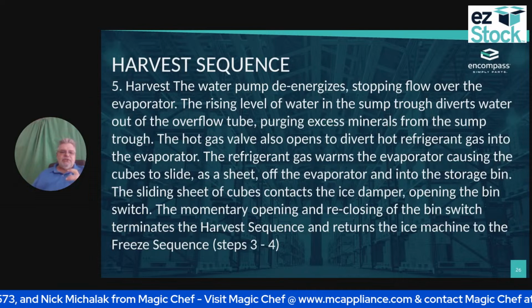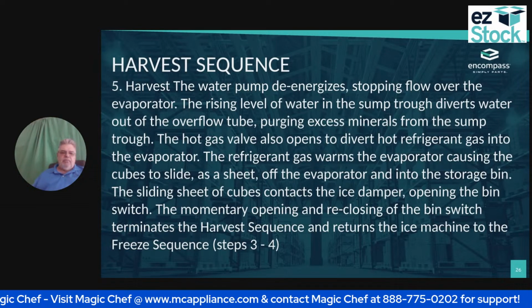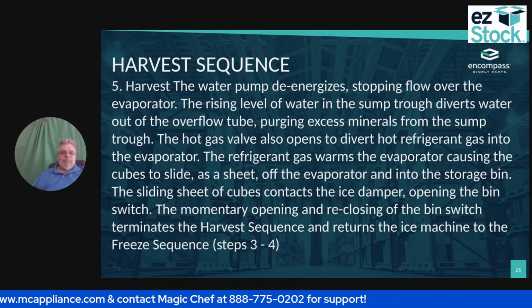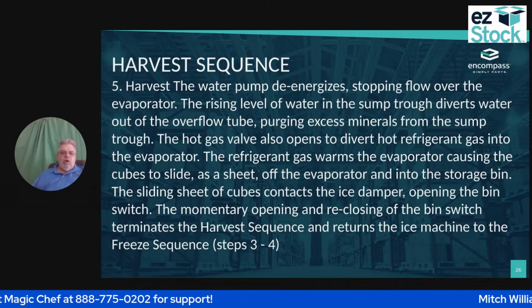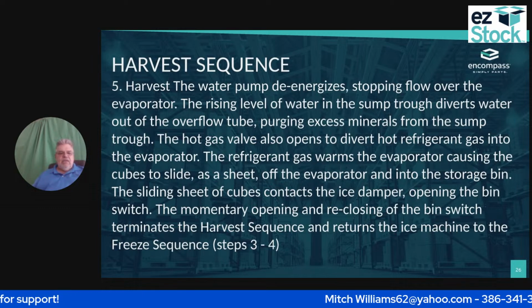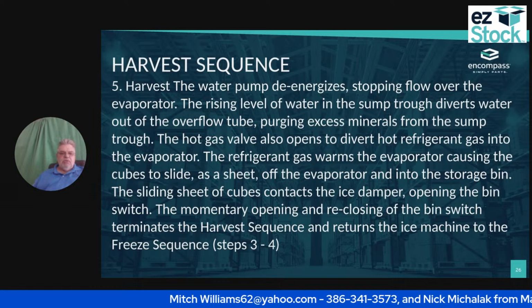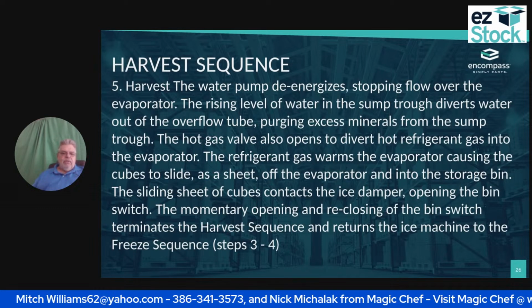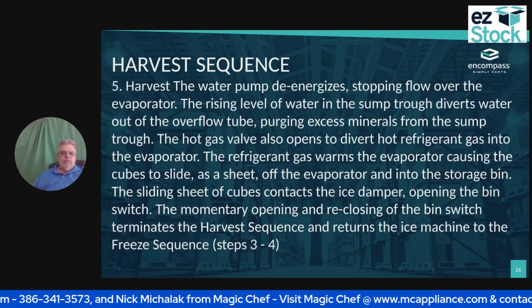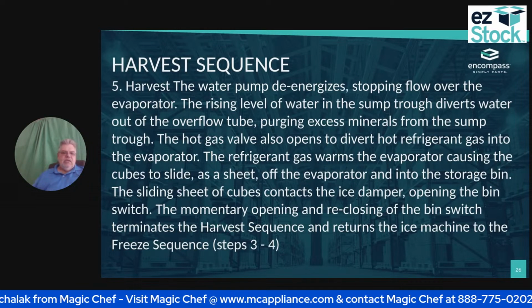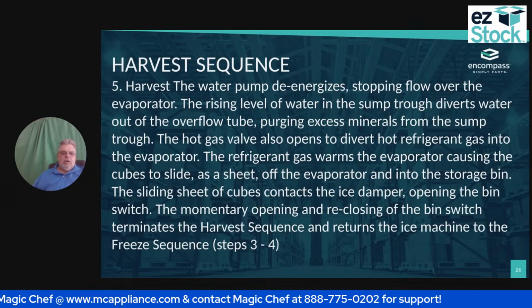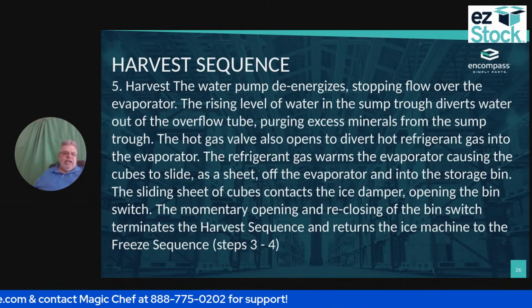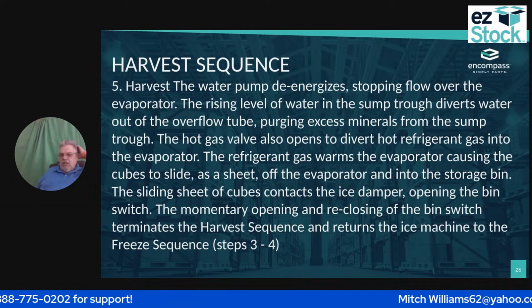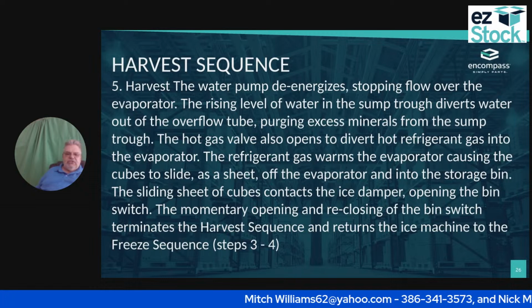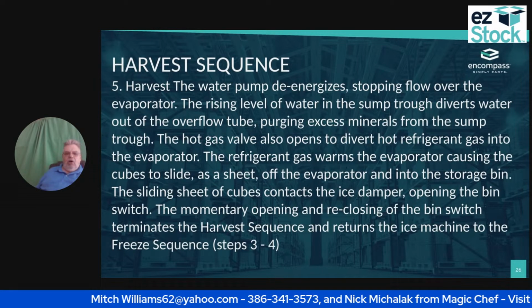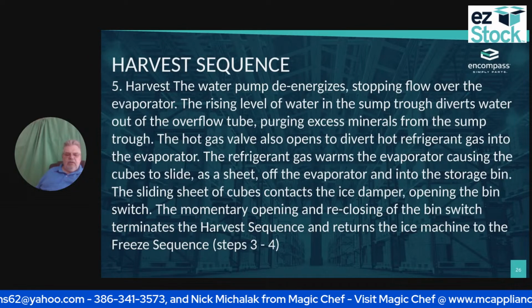So the harvest sequence, what will happen is the water pump de-energizes. That will stop the flow over the evaporator. The rising level of water in the sump trough diverts water out of the overflow, purging excess minerals from the sump. The hot gas valve also opens. It diverts all the hot refrigerant gas into the evaporator. The refrigerant warms the evaporator up, causing those cubes to slide off as one whole sheet. I will tell you that if I have it set really low, it may not all come off as a sheet. It may come out in little pieces and chunks.